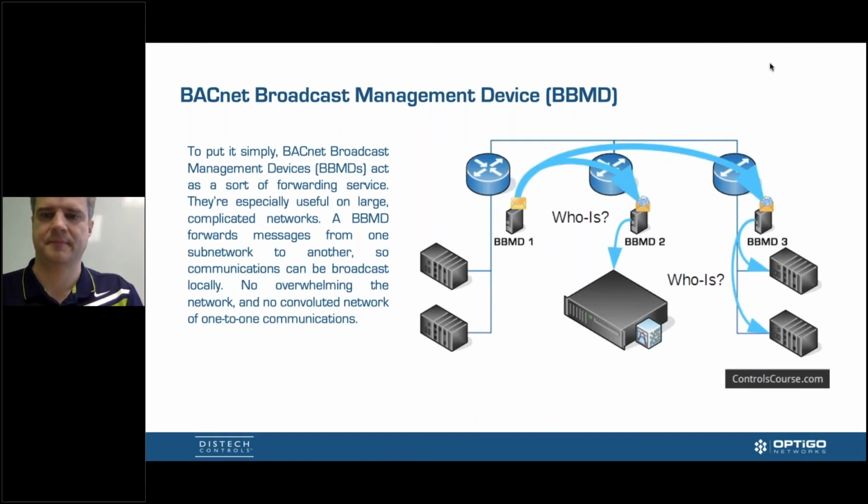We're going to talk a little bit more about that in the live demo, but it's worth stressing. BBMDs are not needed for routing all BACnet traffic. They're specifically needed for routing broadcast traffic. So if you have an IP device on one network and another IP device on another, you don't need a BBMD for them to talk to one another.